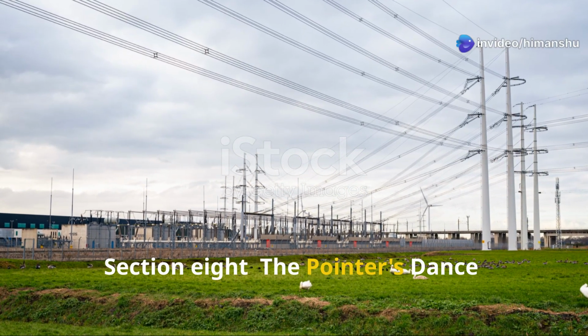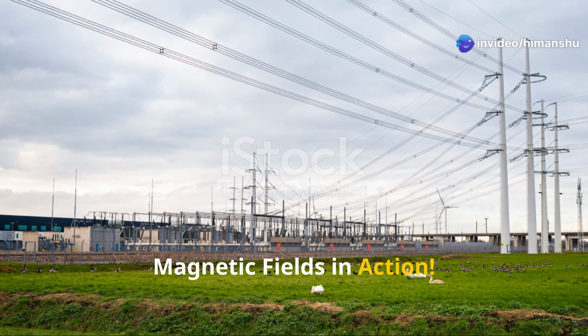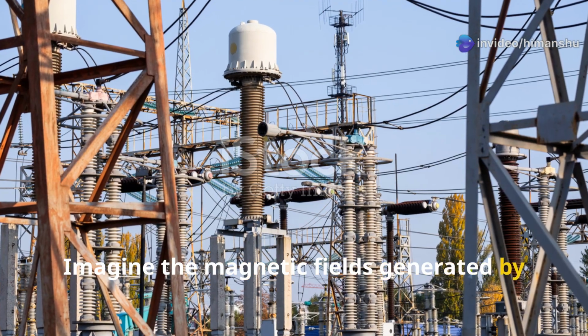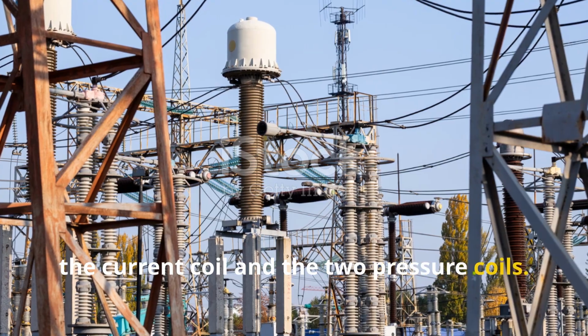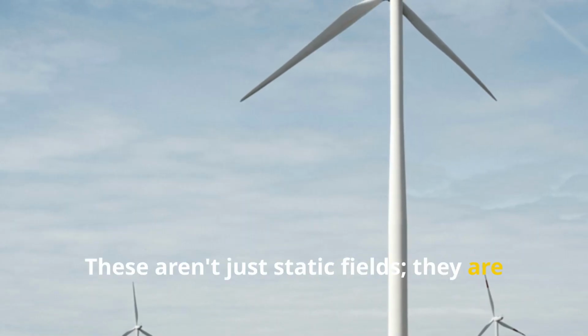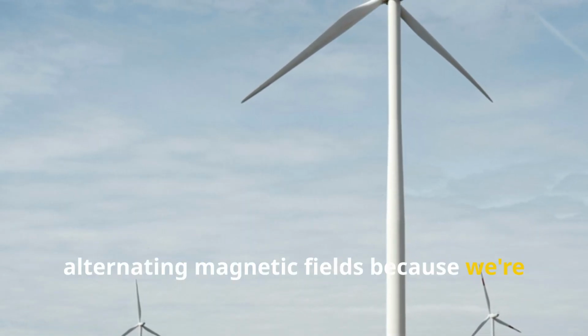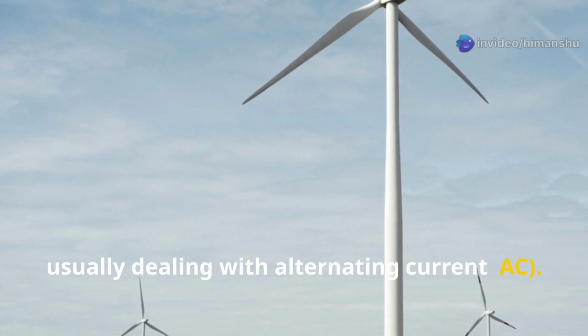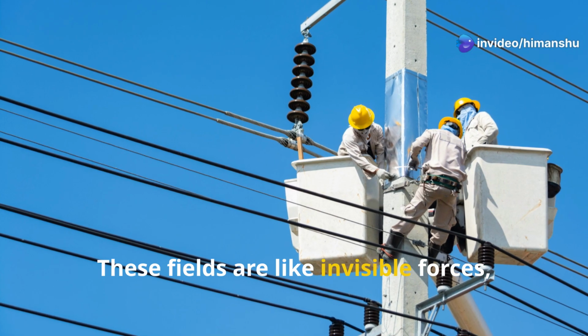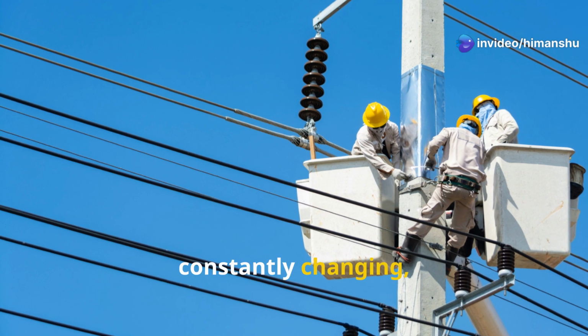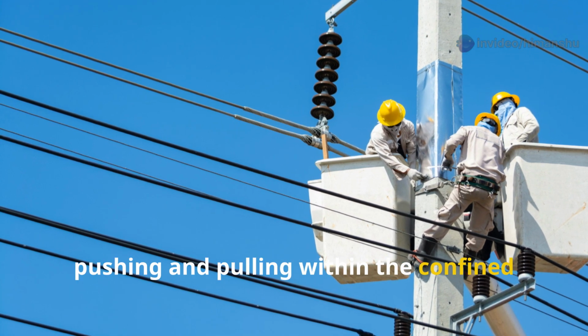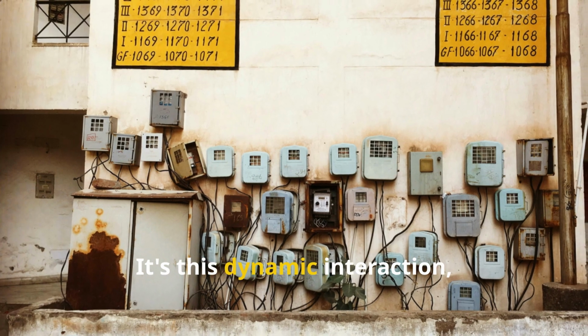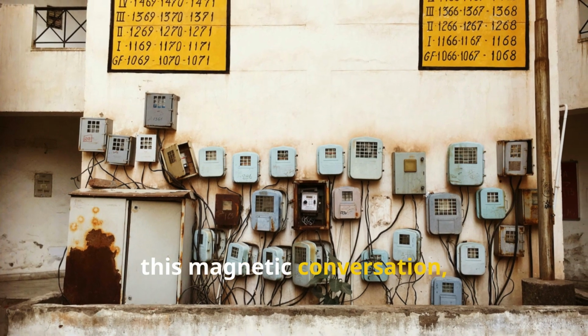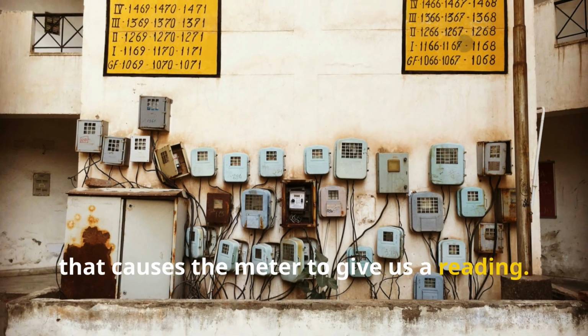Section 8. The pointer's dance: magnetic fields in action. Imagine the magnetic fields generated by the current coil and the two pressure coils. These aren't just static fields, they are alternating magnetic fields because we're usually dealing with alternating current, AC. These fields are like invisible forces, constantly changing, pushing and pulling within the confined space of the meter. It's this dynamic interaction, this magnetic conversation, that causes the meter to give us a reading.